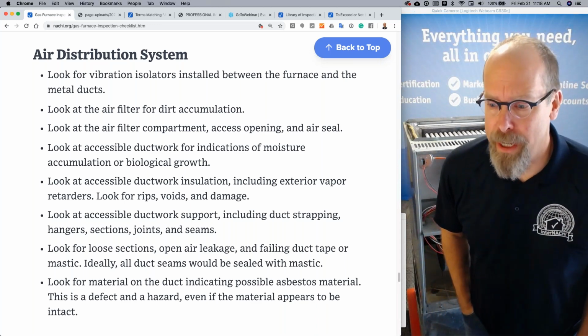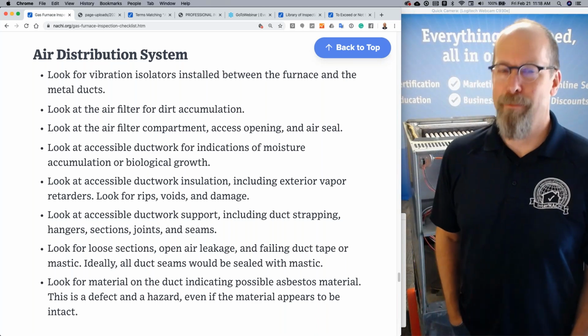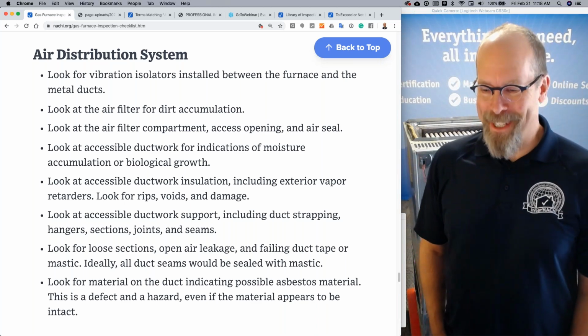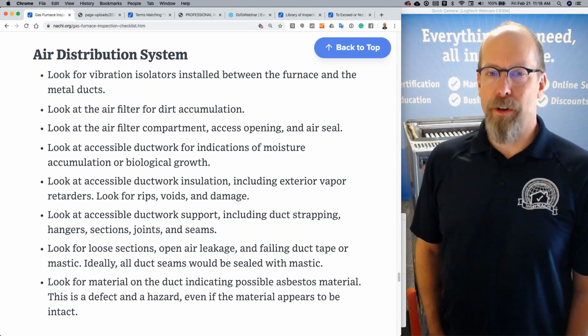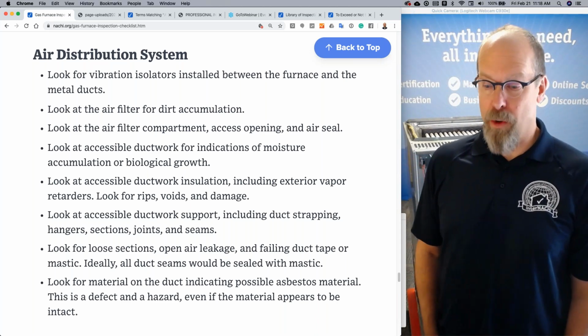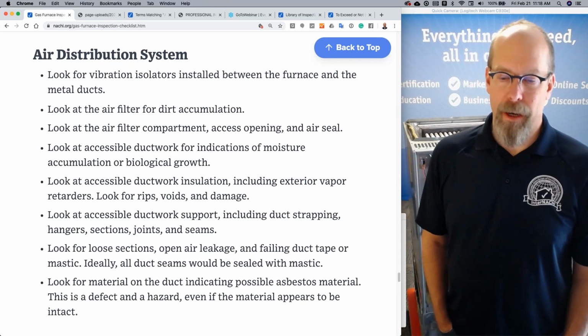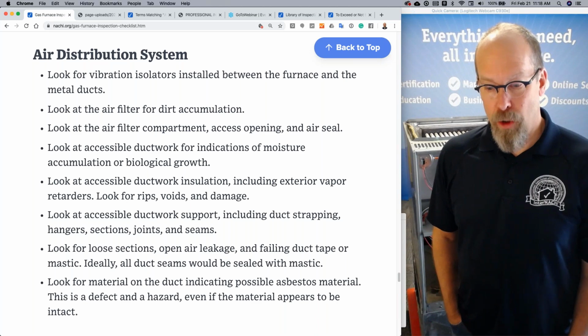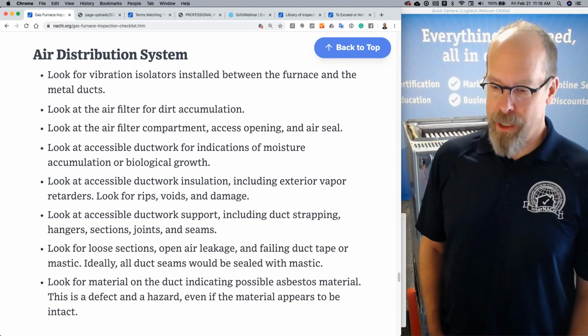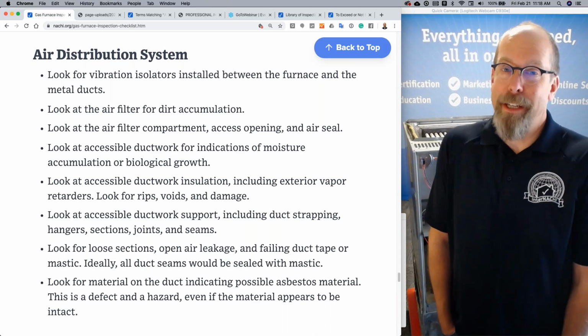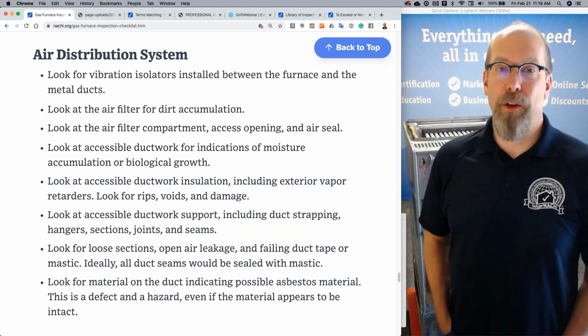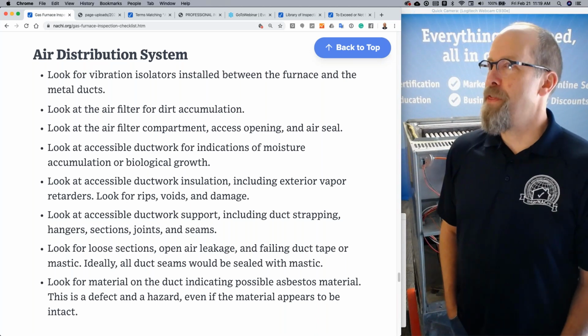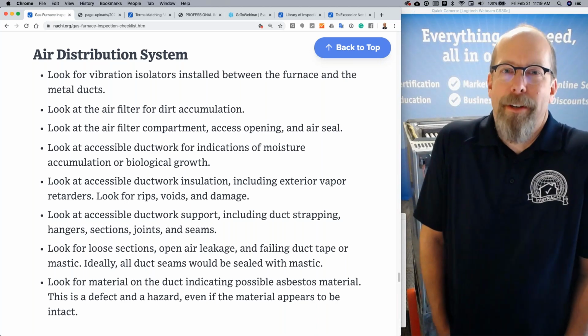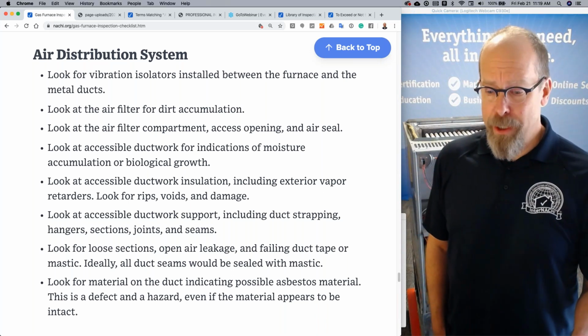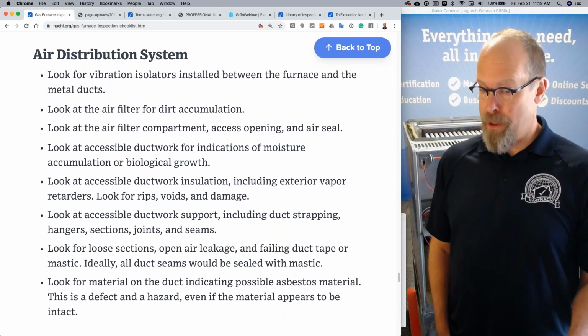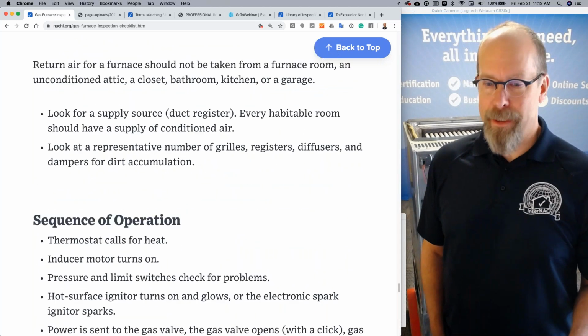Look at the accessible ductwork for indications of moisture accumulation or biological growth, mold. Look at the accessible ductwork insulation, including exterior vapor retarders. Look for rips, tears, and damage. Look at the accessible ductwork support, duct strapping, hangers, sections, joints, and seams. Look for loose sections, open air leakage, failing duct tape or mastic. Ideally, all ducts at the seams would be sealed with mastic. That's like a thick, if you haven't seen it, it's like gray paint, really thick paint. You seal the seams. Look for material on the duct indicating possible asbestos material. It's a defect and hazard even if it appears intact.